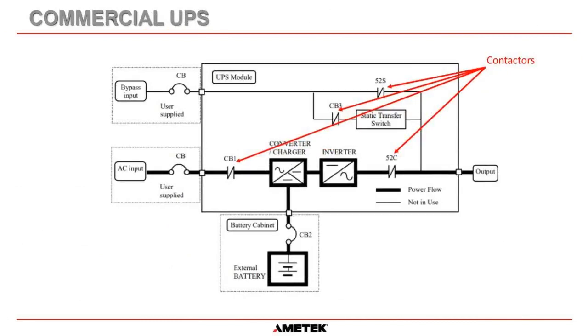Another thing you'll notice about commercial UPSs is that there are contactors inside the UPS — the circuit breakers are actually the buckets inside your MCC. Contactors have moving parts, coils, and can pull in and drop out. The contacts can weld and the coils can burn out. Unfortunately, contactors can and do fail. We do not like using contactors in our UPS, but in many commercial UPSs they are used.